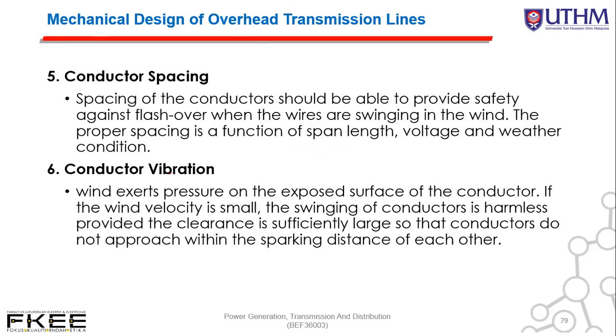Conductor spacing. Spacing of the conductors should provide safety against flashover when the wires are swinging in the wind. The proper spacing is a function of span length, voltage, and weather condition. Finally, conductor vibration. Wind exerts pressure on the exposed surface of the conductor. If the wind velocity is small, the swinging of the conductor is harmless, provided the clearance is sufficiently large so that conductors do not approach within the sparking distance of each other. So that's all for our class in chapter 4 today.